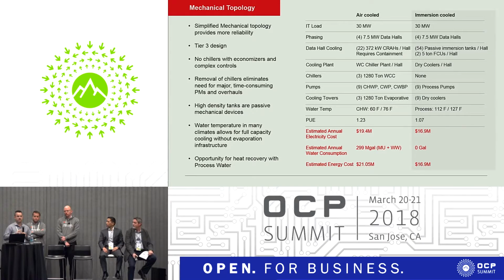From the plant side, we've gotten it down to where all you have are circulating pumps and dry coolers. It's the only thing you have left to reject the heat from the tanks out to the outside world. Because of the operating temperatures of the fluid itself and the IT equipment, we don't need any evaporative pre-cooling of any of the heat rejection media. This is a 100% dry system. And so you see when we get down here to the estimated annual water consumption, we're talking about going from nearly 300 million gallons a year for a 30 megawatt load down to 0. And obviously the PUE delta here.